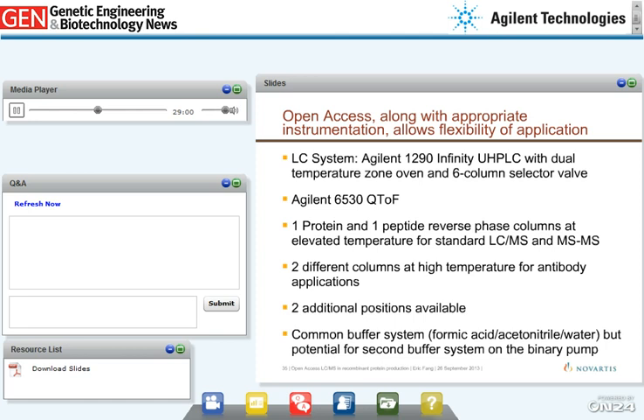We've implemented open access on an Agilent 6530 QTOF with a 1290 UHPLC system, but a lot of what I've discussed can be done on lower-resolution instruments. We also selected a six-column selector and dual temperature zone column oven, allowing us to have separate protein, peptide, and antibody columns held at different temperatures. This means we can offer protein, peptide, and antibody methods all in the same system. Different users with different needs can queue up their diverse samples and the system works through them without intervention — a real advantage in flexibility.